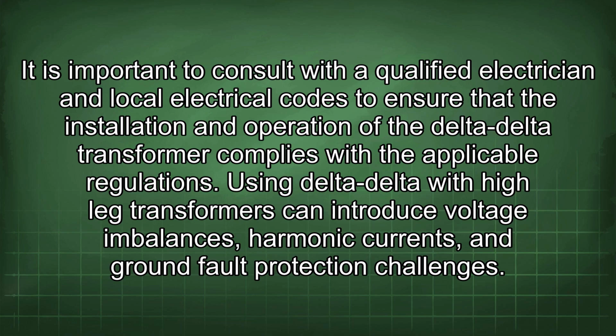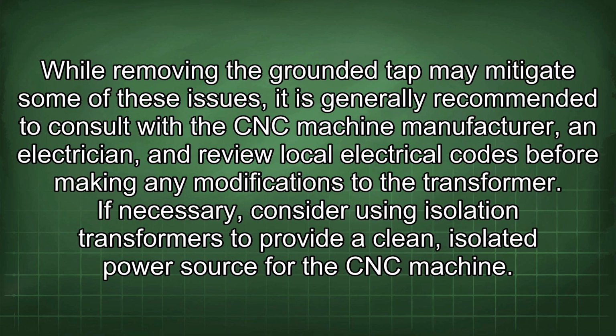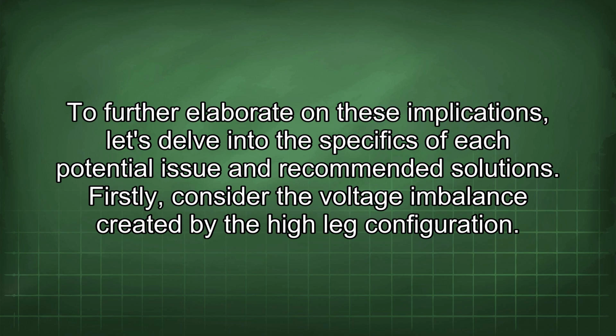Using delta-delta with high leg transformers can introduce voltage imbalances, harmonic currents, and ground fault protection challenges. While removing the grounded tap may mitigate some of these issues, it is generally recommended to consult with the CNC machine manufacturer, an electrician, and review local electrical codes before making any modifications to the transformer. If necessary, consider using isolation transformers to provide a clean, isolated power source for the CNC machine. To further elaborate on these implications, let's delve into the specifics of each potential issue and recommended solutions.